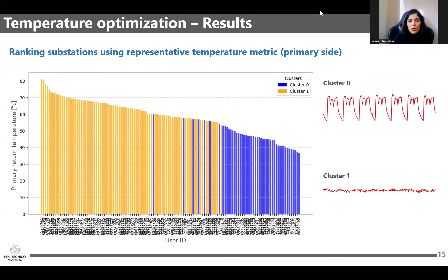So we followed the same procedure of clustering and assigning the representative temperature also for the secondary return and secondary supply temperature. At the end, for each of these 50 substations, we had three representative temperature metrics, and from these we started to calculate some key differential temperatures that could give hints to the operator about the possible root of these inefficiencies.